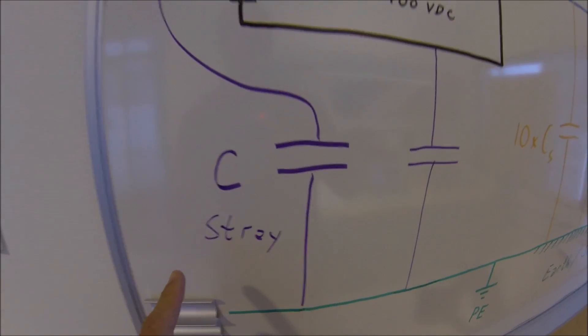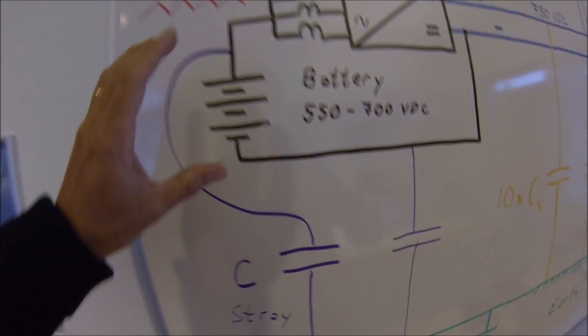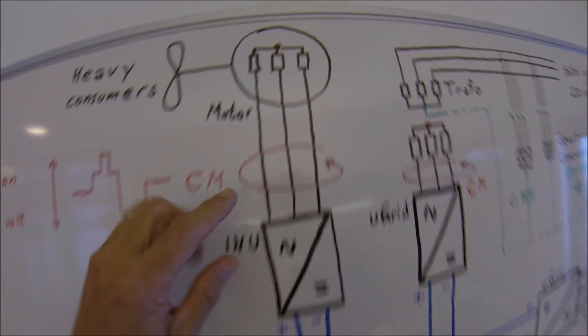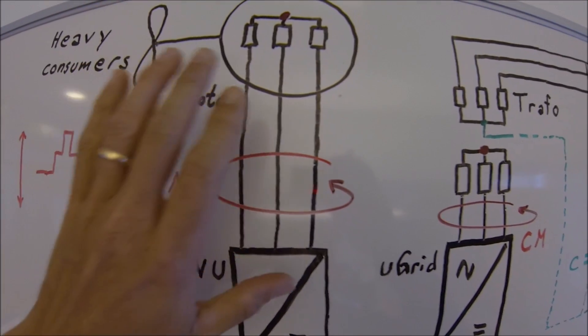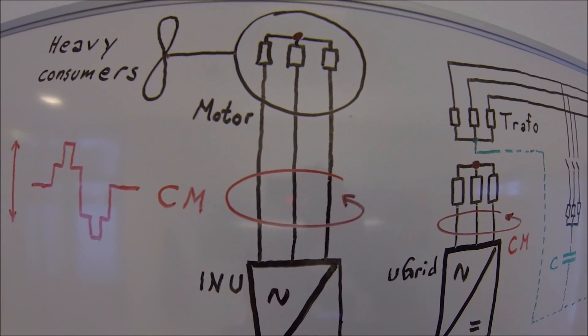And this stray capacitance is the summary of the stray capacitance in your battery, but also in your motor cables because these ones have big surface area to protective earth. And there is a certain capacitance there which will make some kind of anchoring of the system.